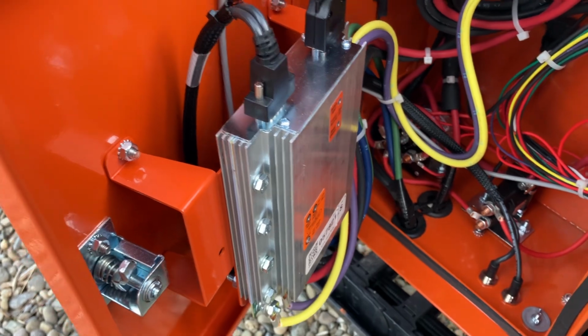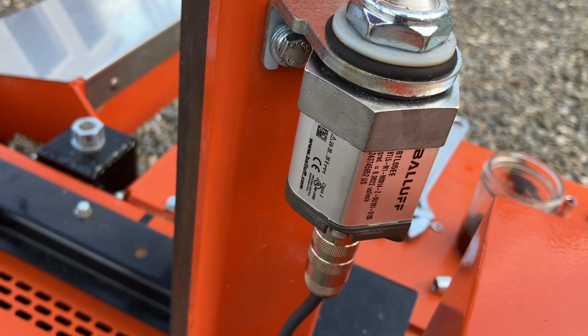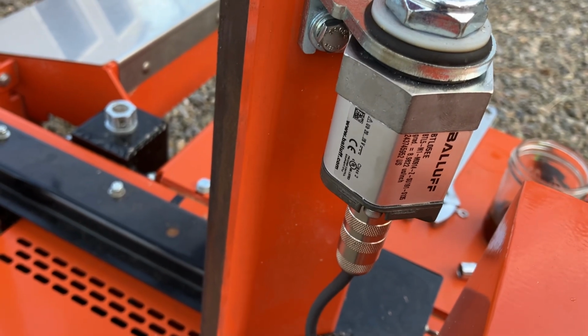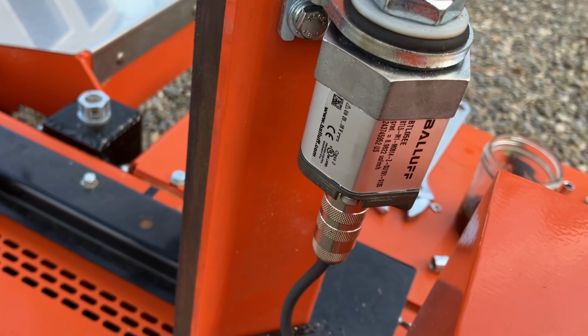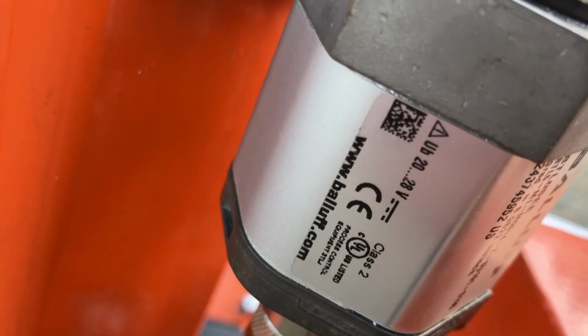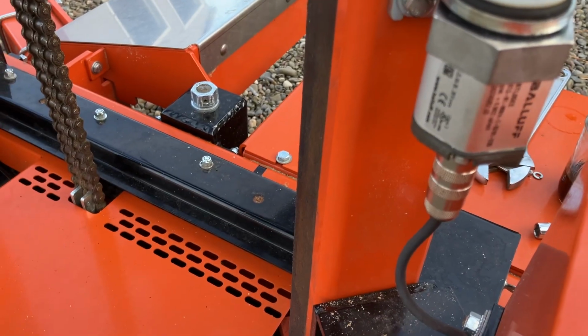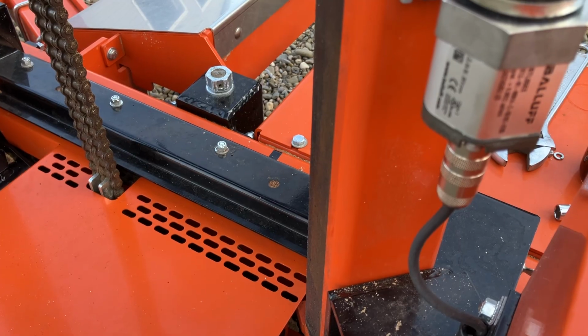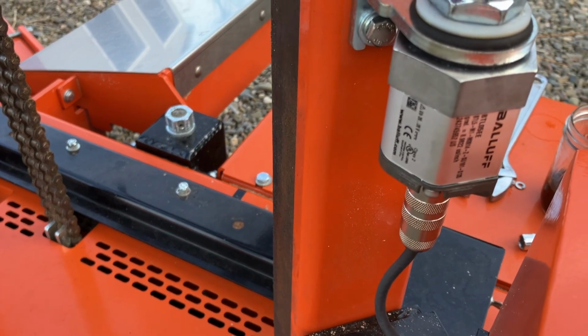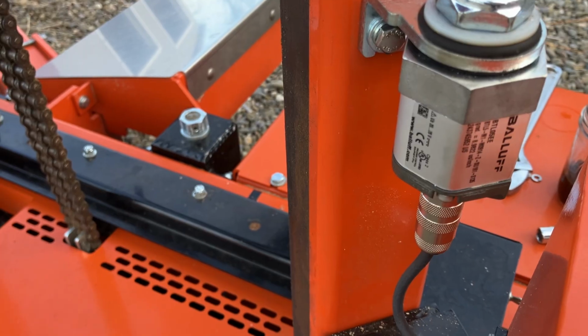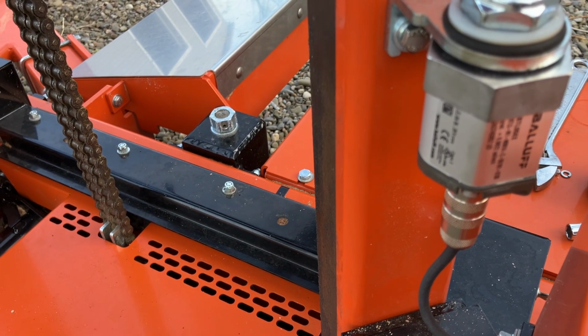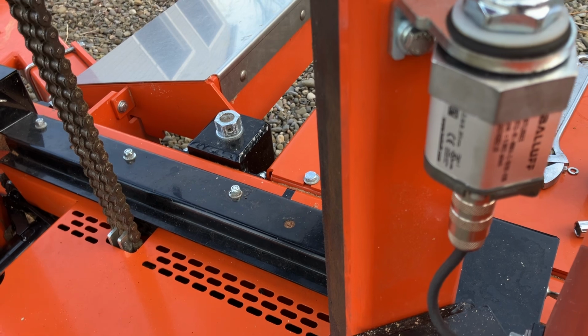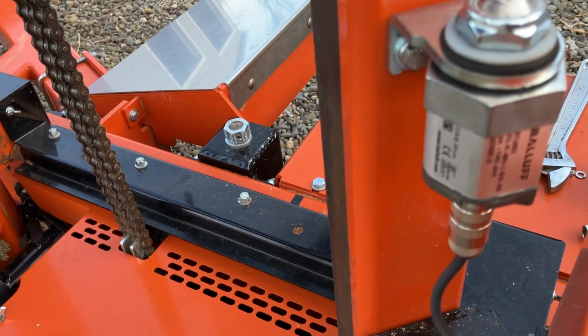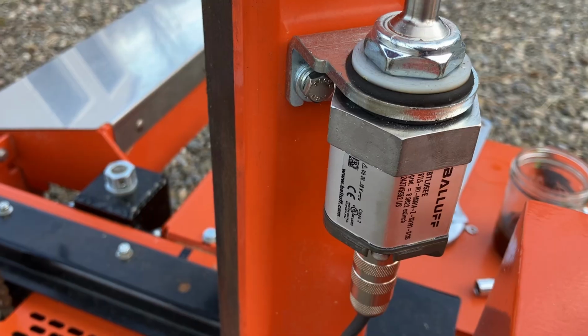So the linear encoder is 12 volts. I'm sorry, it's 24 volts, standard, more standard industrial DC power voltage. So basically, there was a short internally inside the transducer, which is drawing the 12 volts down, or 24 volts down, which reduced the 5 volt output through the potentiometer, so we weren't getting the correct voltage coming back for your speed control forward. So that ended up being the problem.